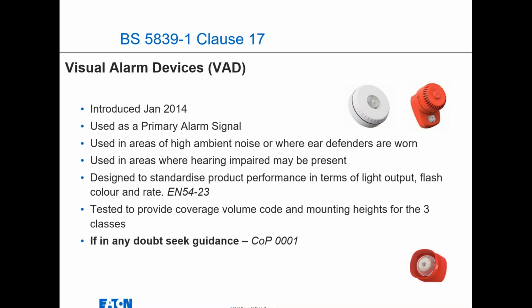Mostly if you put a VAD in a small room, you'll be covered. It's only when you start building up lots of VADs in big spaces that you can sometimes fall foul. And again, they genuinely come into play in that scenario in large projects. Most of the small ones, whether that's ceiling mounted or wall mounted, you can usually comply, as long as they're in line with the detection standards as well. So if you've got an L1 system, you should have virtually as many VADs as smoke detectors. So if there's one smoke detector, you need one VAD. If there's then 2 smoke detectors, you'll probably need 2 VADs.